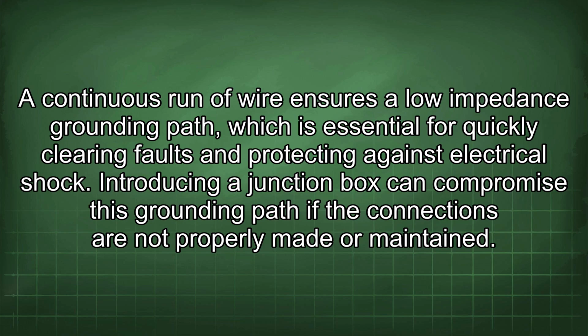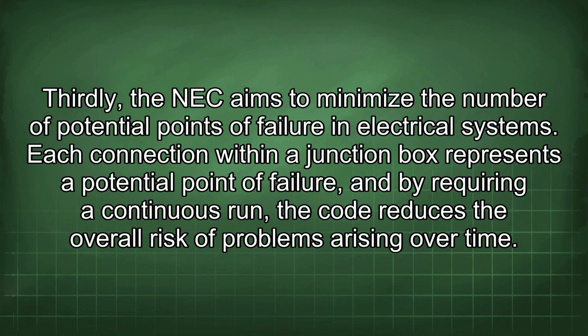Secondly, the integrity of the grounding path is crucial in these circuits. A continuous run of wire ensures a low impedance grounding path, which is essential for quickly clearing faults and protecting against electrical shock. Introducing a junction box can compromise this grounding path if the connections are not properly made or maintained. Thirdly, the NEC aims to minimize the number of potential points of failure in electrical systems. Each connection within a junction box represents a potential point of failure, and by requiring a continuous run, the code reduces the overall risk of problems arising over time.